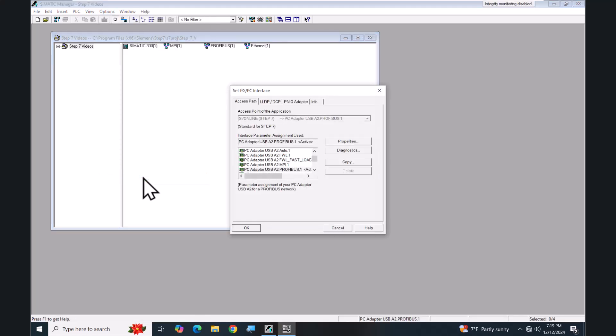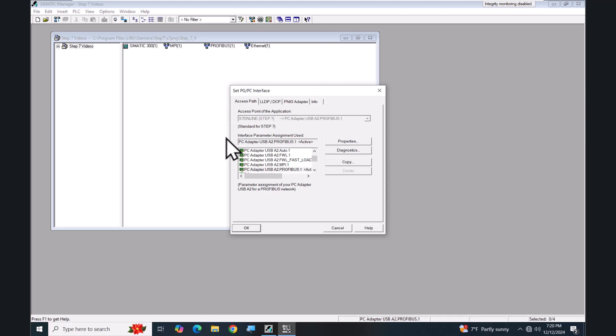In the Set PG/PC interface dialog box, the first thing is the access point of the application. This is always going to be S7 Online for the Step 7 connection to the PLC. Then you are going to tie a physical adapter with the interface parameter assignment used area to the S7 Online logical access point of the application. Currently PROFIBUS is selected, so I'll select Properties.